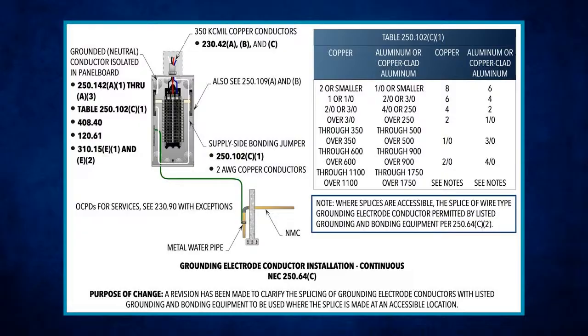When you get over to C, this is where they talk about it being continuous. These grounding electrode conductors are required to be installed in one continuous length without any splices or joints—that's what they added, the splices or joints—by one of the means we're about to talk about. This is a general requirement, but they say except as provided, referring you over to 250.30, I think A5, A6, and B1, which deals with separately derived systems. And then they also reference 68C.